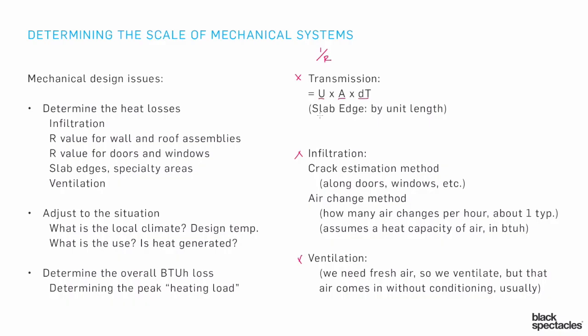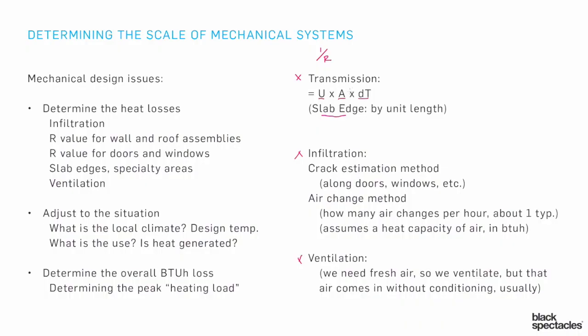Most of this is done by area — by different wall assemblies, floor assemblies, and roof assemblies. But there are a few exceptions, like slab edge, where it's done by unit length. The way heat is lost from a slab on grade is through the edge of the slab, so you multiply a unit length number times the actual perimeter distance around that slab. Not everything falls exactly into the area-per-square-foot situation, but most of it does. Adding up all those numbers gives us our total heat loss for transmission in BTUH.